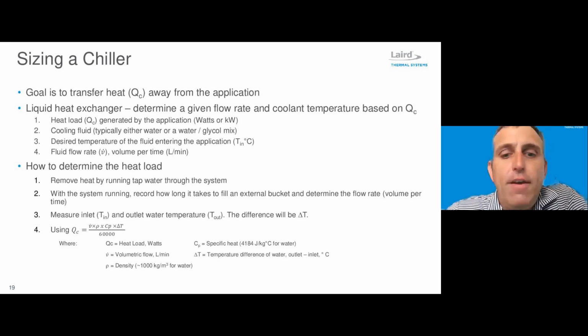Okay, great, thanks. We have another question here that says, how easy is it to manage the exhaust heat? Yeah, so this can be done a couple of ways. The first is that the system can always be installed in the location of use of the end instrument, and we just need to keep in mind the amount of heat that's being rejected into the environment. One, for a comfort level of the user, we want to make sure we're not pouring too much heat onto them, but then also we need to make sure that the air conditioning or the HVAC system can handle this additional load.